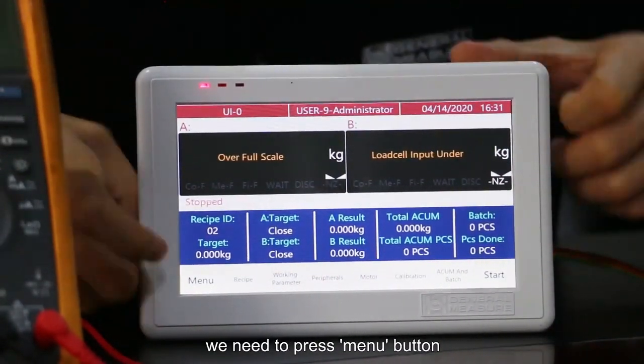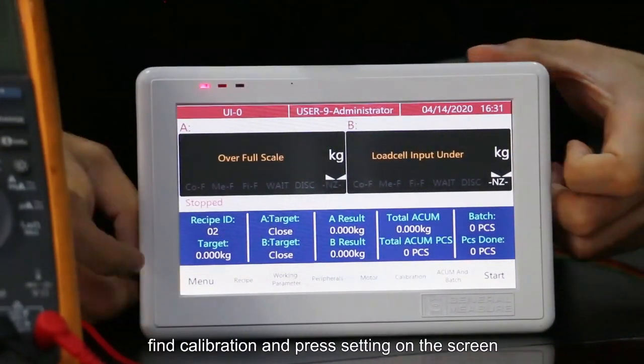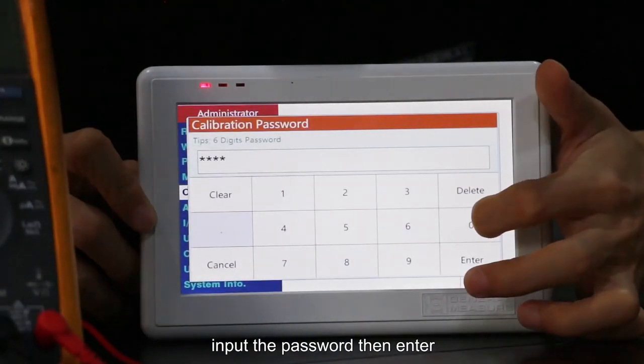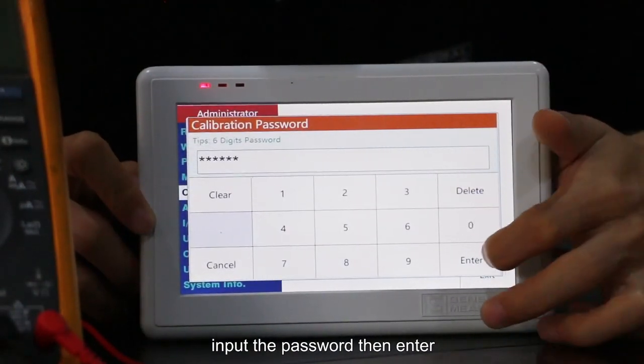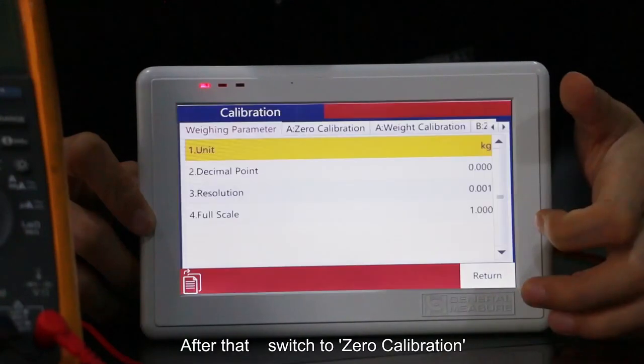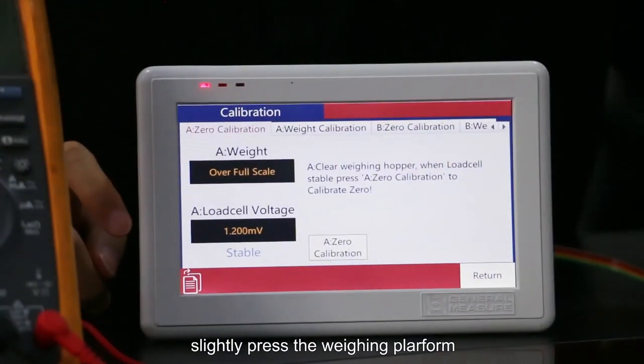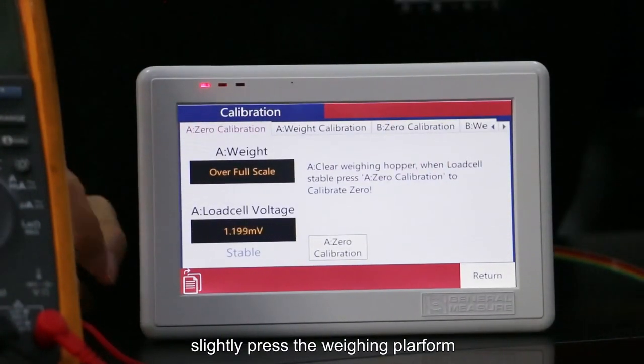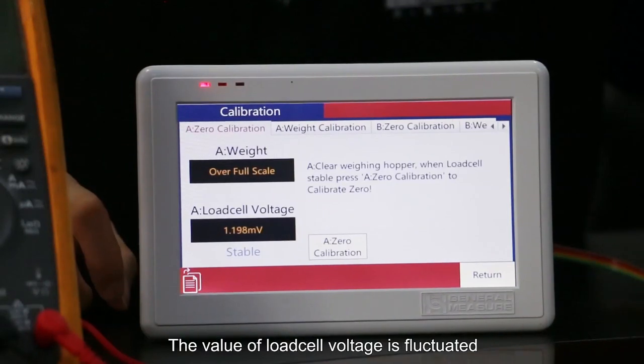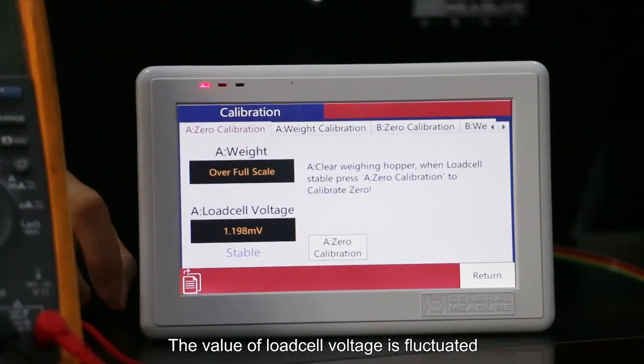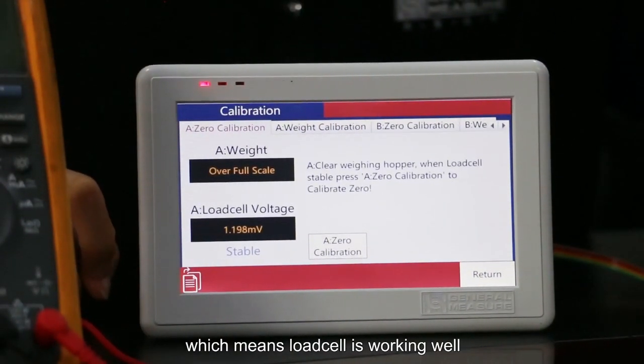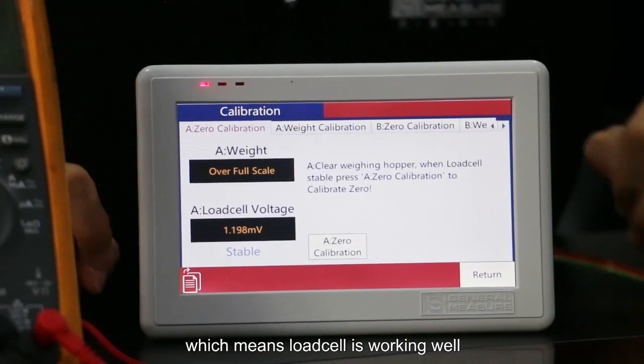In this situation, we need to press the menu button, find calibration, and press setting on the screen. Input the password, then enter. After that, switch to 0 calibration and slightly press the weighing platform. The value of load cell voltage is fluctuating, which means the load cell is working well.